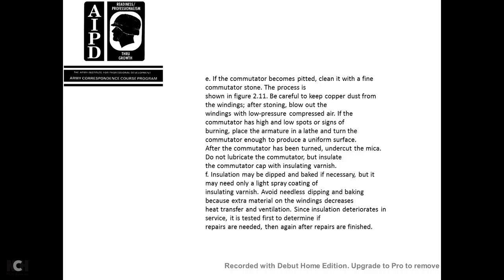Be careful of the copper dust from the windings; after the stone is used, blow out the windings with low pressure compressed air. If the commutator has high and low spots or signs of burning, place the armature in a lathe and turn the commutator enough to produce a uniform surface.